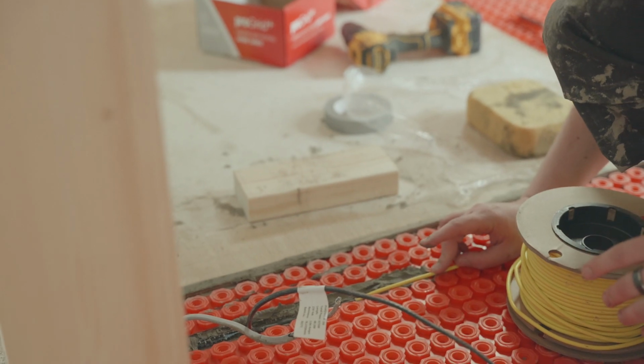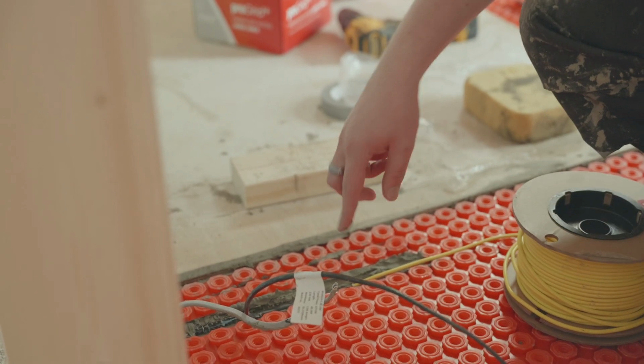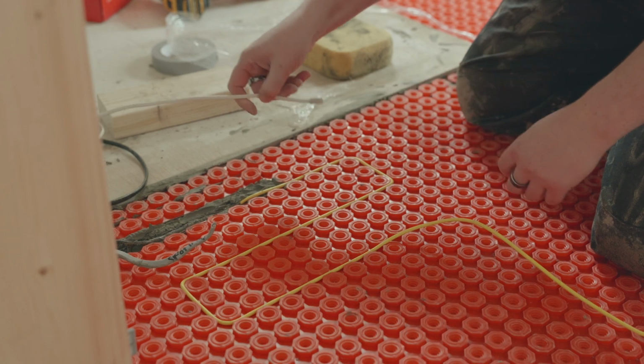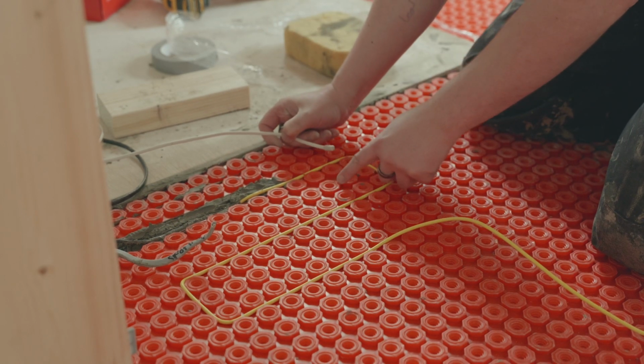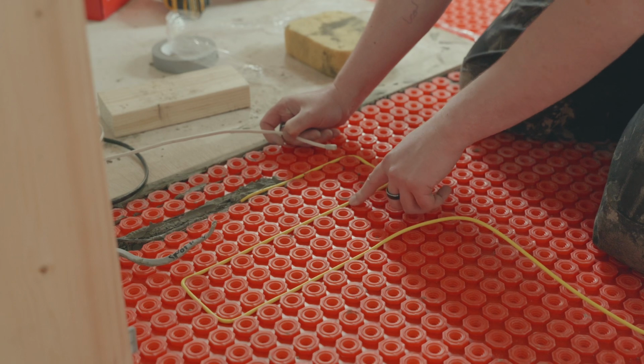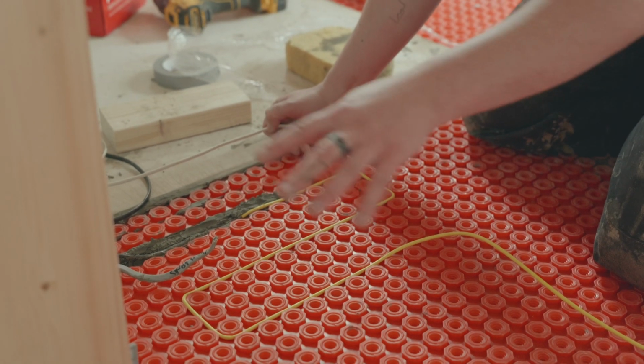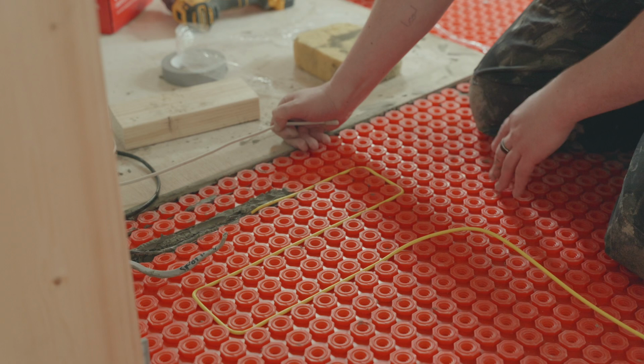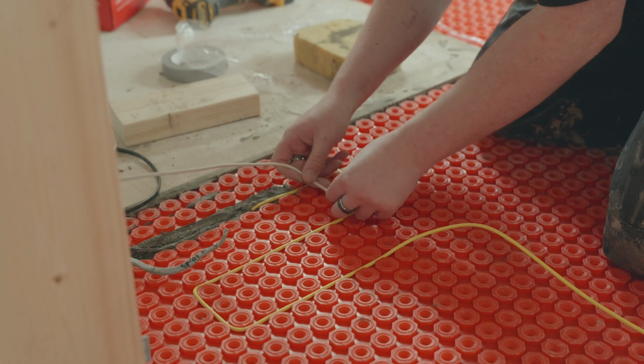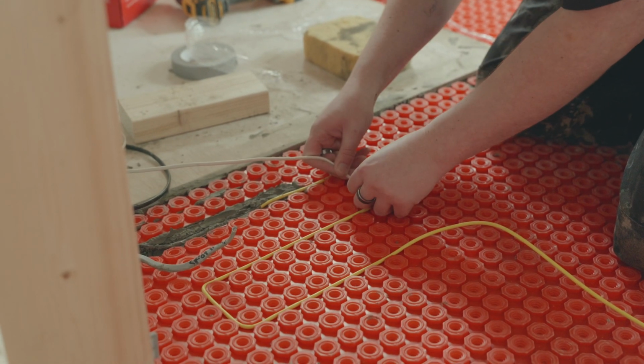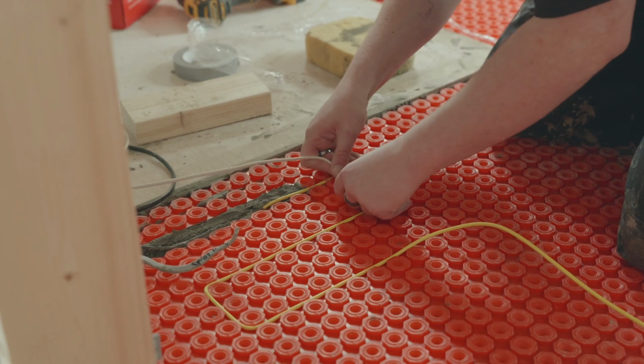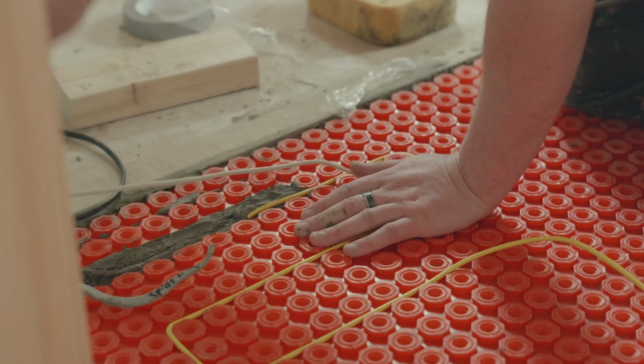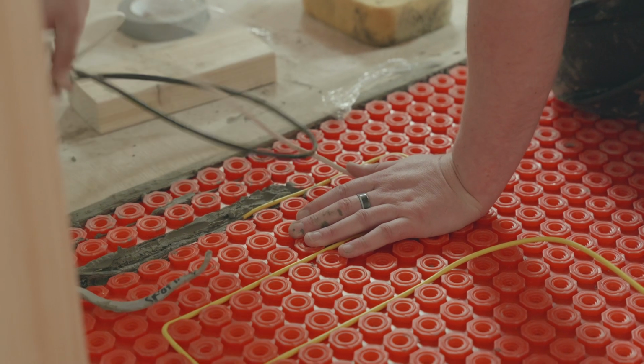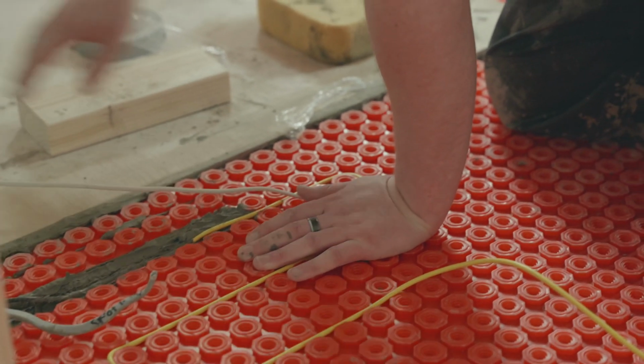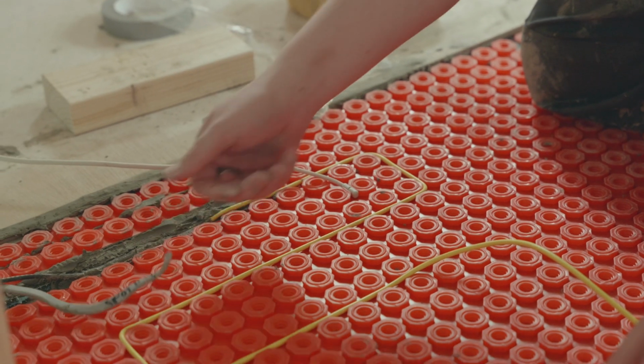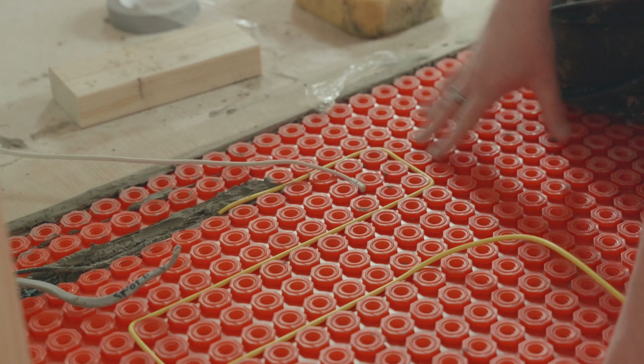and we're going to take the opportunity at this point as well to install our floor probe. Now the floor probe should be positioned exactly in the center of two heating elements. That's so it picks up a good solid reading of what the ambient floor temperature is. I'm just going to place ours around about here, and then I'm going to put this and the power lead just to one side. Later on we'll attach them to the draw cable and we'll pull them through to the thermostat on the other side of the wall.